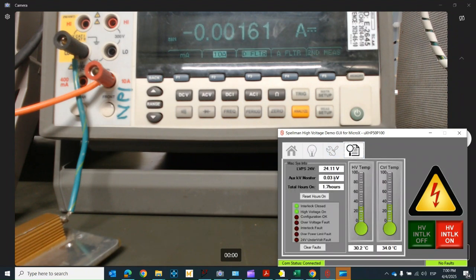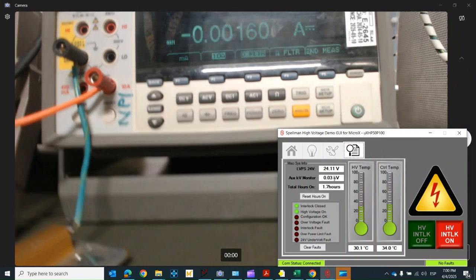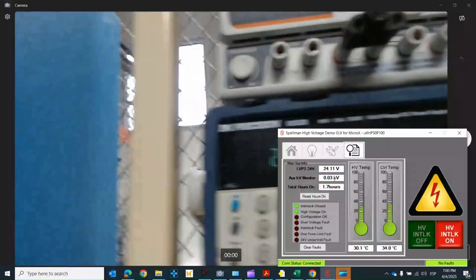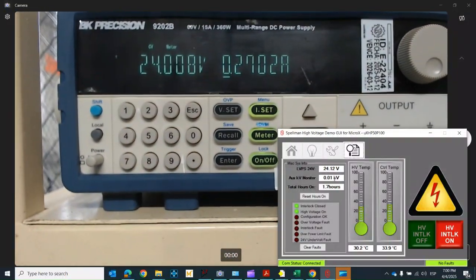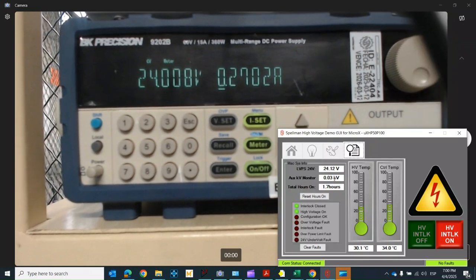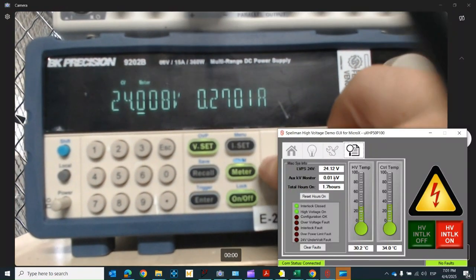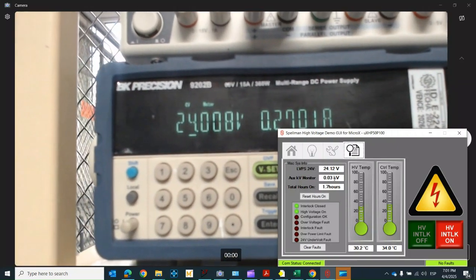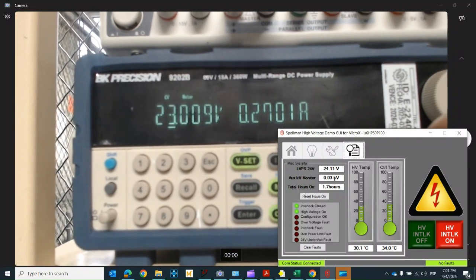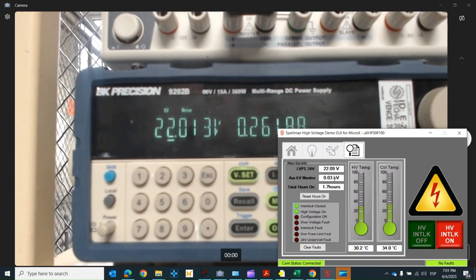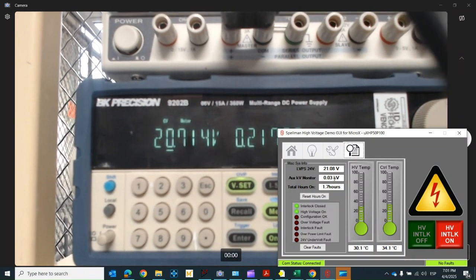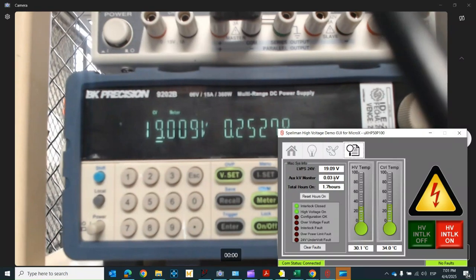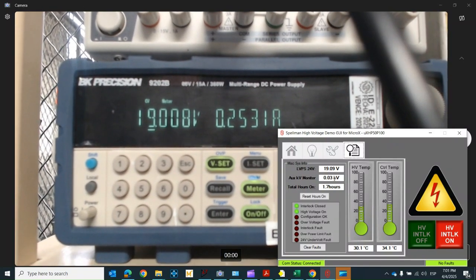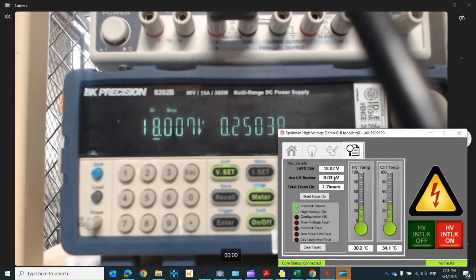Lastly, we will conclude the self-diagnostic test with the undervoltage fault test. With the unit powered off, we will proceed to close the interlock and then begin decreasing the power supply voltage until an undervoltage fault is issued. As with other faults, power on LED should be blinking and high voltage on LED should be off. Undervoltage fault should be issued at 18V plus minus 2V. It can be seen that undervoltage fault occurs at 17.9 volts.